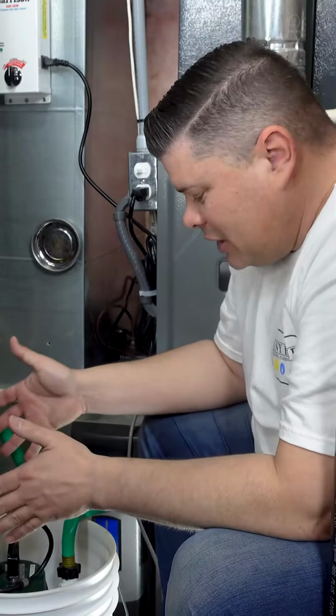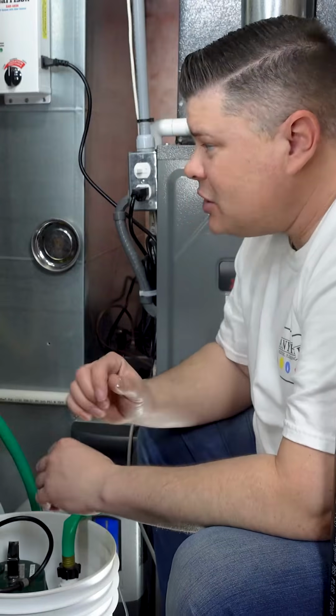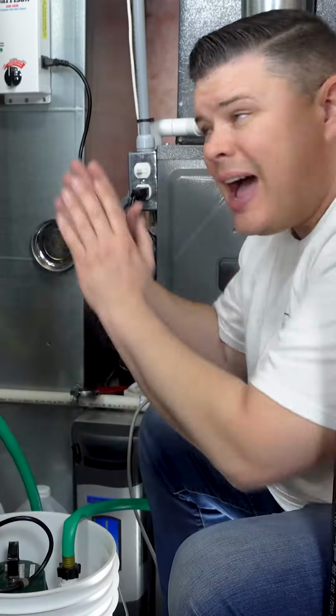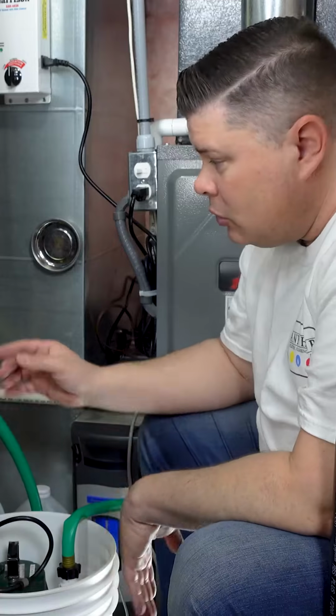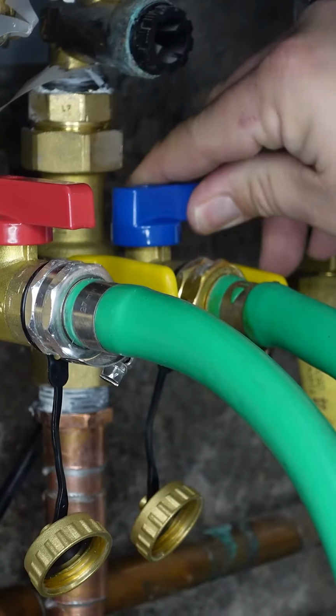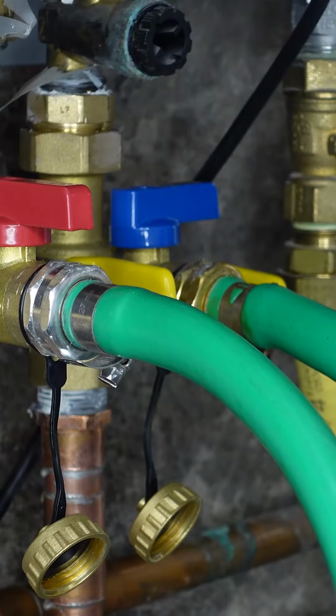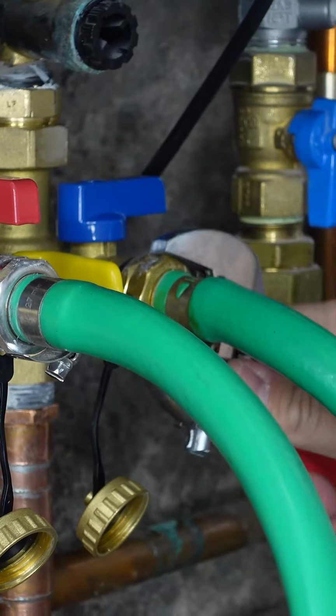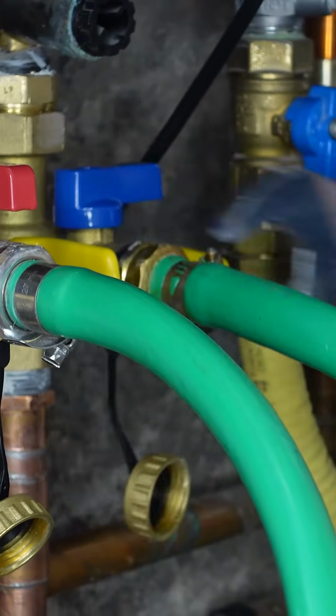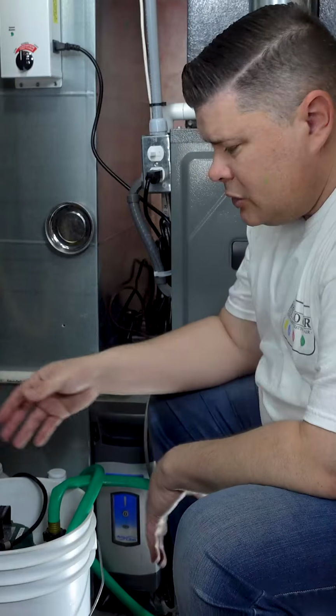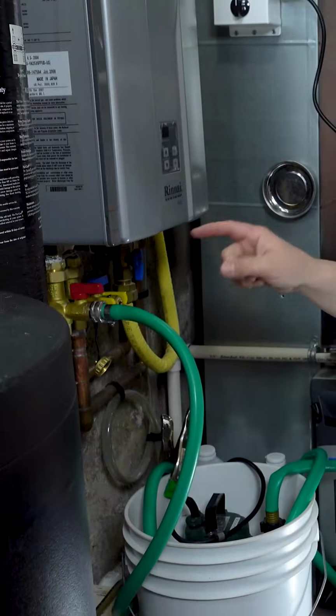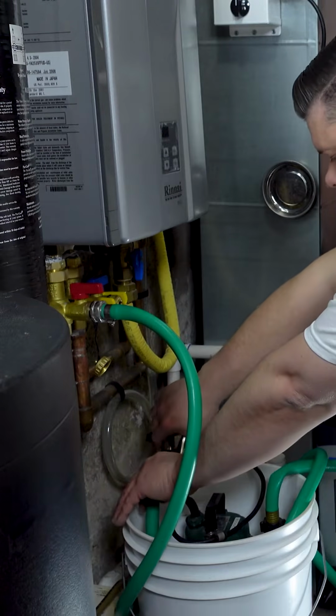Now that we're done flushing the tankless, what we need to do is actually rinse the cleaning solution out of the heat exchanger. So what we're going to do is close the service valve that the pump was attached to, and we can go ahead and remove the pump right now. So we're going to take the end of the hose that's coming off of the hot side of the tankless.